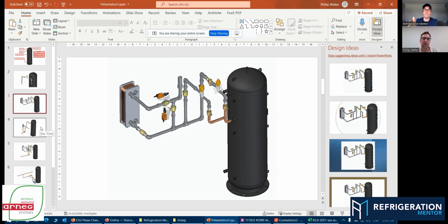So you only have that valve there when it gets so cold out. Well, once again, it all goes back to how you're cutting the gas cooler up in cold environments, like your circuitry for your gas cooler. We were working on a project this morning with a customer, and we have 5 circuits on the gas cooler. I think it's really intelligent how they wanted to do this, because they understood load is going to be so minimum at certain applications that they need a minimum percentage to circulate mass flow. Well, that just states that if the customer is willing to understand that, the design has to understand that as well, right? So hence, we can't have just that one big valve, because it is just going to close, cause a holdback.